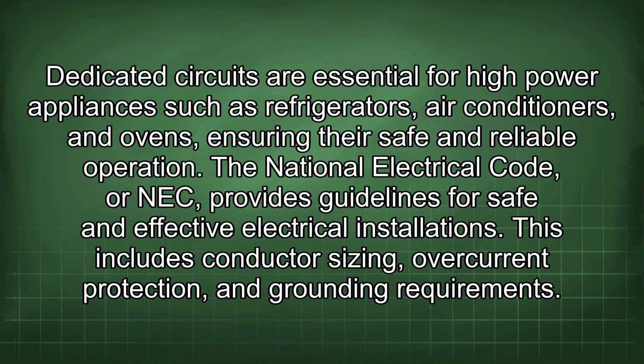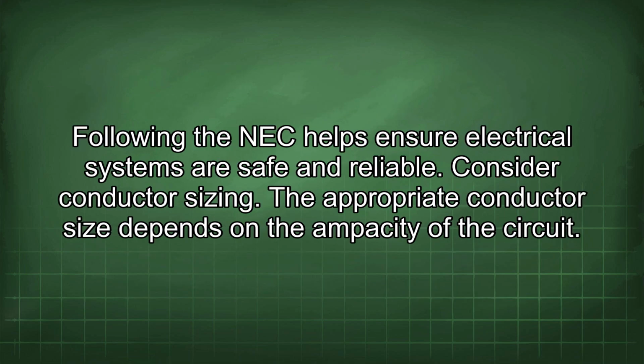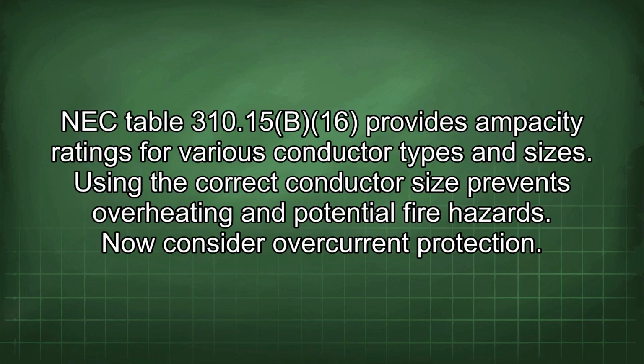The National Electrical Code, or NEC, provides guidelines for safe and effective electrical installations. This includes conductor sizing, overcurrent protection, and grounding requirements. Following the NEC helps ensure electrical systems are safe and reliable. Consider conductor sizing. The appropriate conductor size depends on the ampacity of the circuit. NEC Table 310.15(B)(16) provides ampacity ratings for various conductor types and sizes. Using the correct conductor size prevents overheating and potential fire hazards.